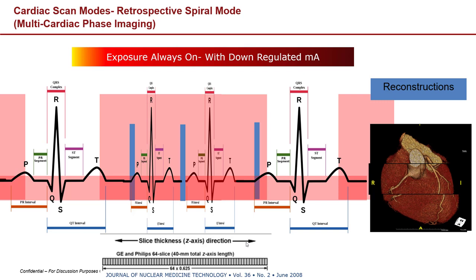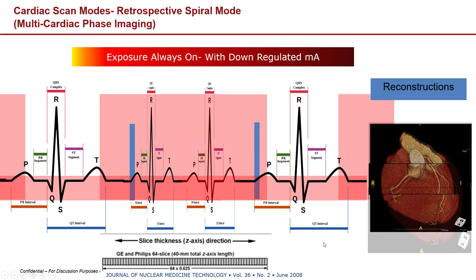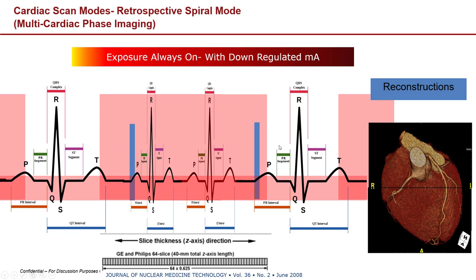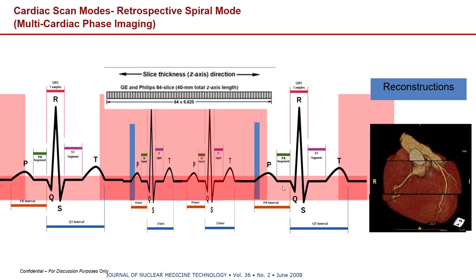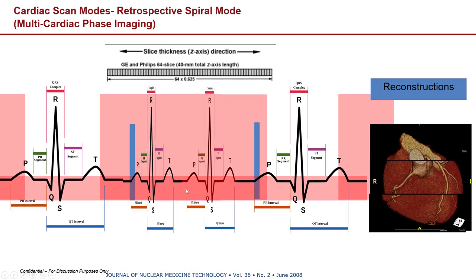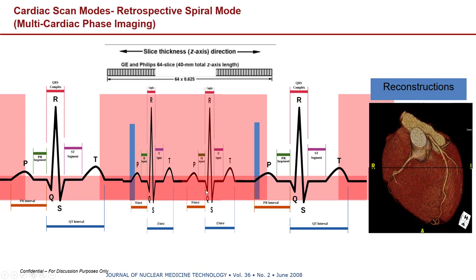With retrospective gating, you don't have to re-scan the patient. You can omit that reconstruction and force the scanner to reconstruct from the two adjacent reconstruction windows. Because you're moving over the heart very slowly, you can tell the system not to use that central detector but to use the peripheral detectors instead, capturing that image with less artifact.